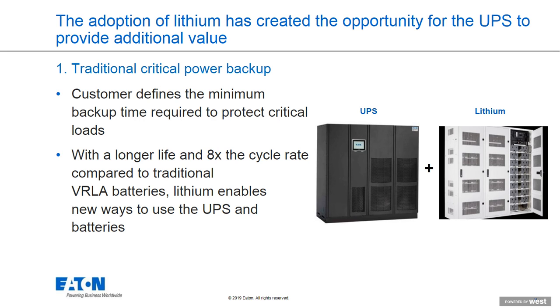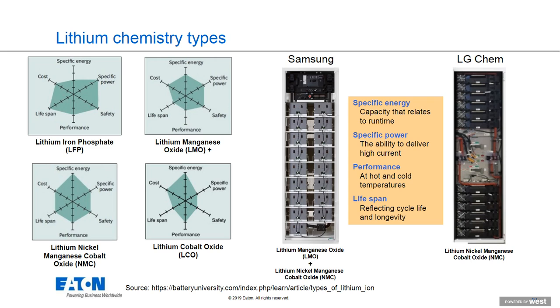As we said, the adoption of lithium has created the opportunity to use a UPS to provide additional value beyond critical power backup. With a longer life and higher cycle rate compared to traditional VRLA batteries, lithium-ion technology opens the door to new capabilities without having to redesign UPSs from the ground up.